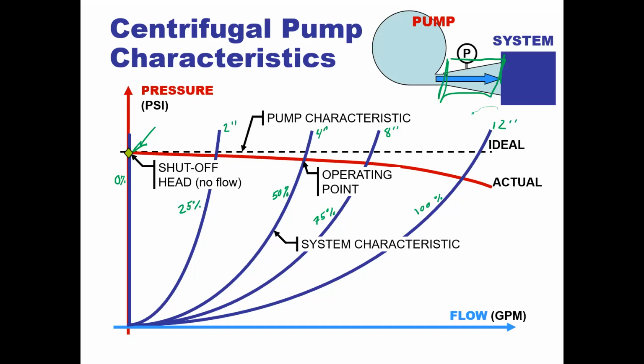We're not going to be moving a liter, a gallon of water into there ever with it being at full no flow scenario, no matter what. If we have a valve that's closed, no more flow, but we'll be maintaining our pressure. Whatever this pressure is, we'll say it's like 60 PSI. It will just stay there and it's not going to harm the pump. But if you keep it there for a couple days, you would harm the pump, because we're imparting kinetic energy into it. And that energy has to go someplace, and what it will become is heat energy. It will basically boil off any of the liquid that's in there, it will turn into a gas, become its own problems.